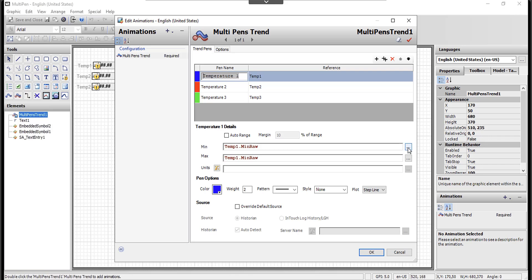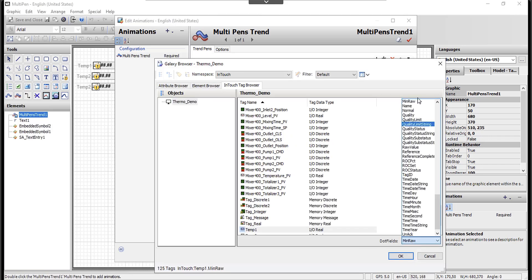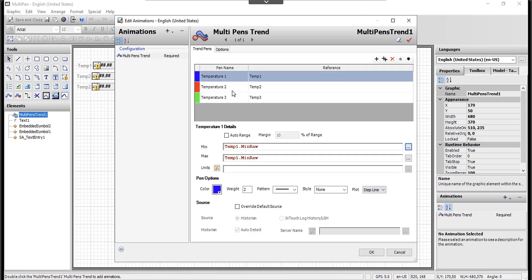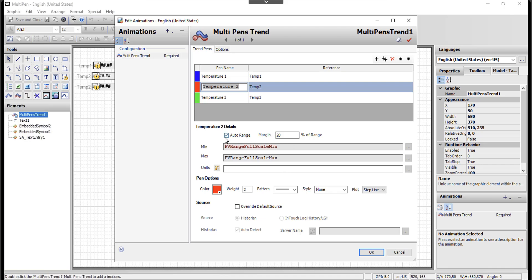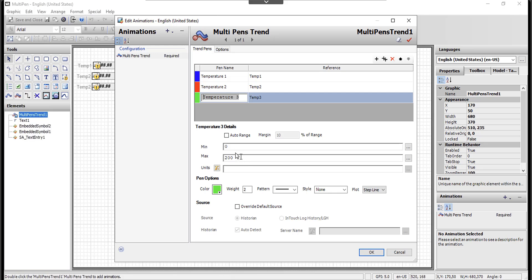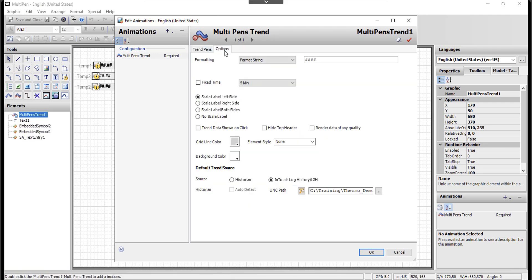For the first pen I chose a dot field for the minimum and maximum. For the second pen I set an auto range with a margin of 20%. For the third pen I gave fixed numbers for the scale. You can choose different colors, weights, and patterns for the lines. Coming back to options, for the default trend source you can choose historian or InTouch log history — the LGH files — which is what I chose. You also need to specify the UNC path, which in our case is the same application directory.